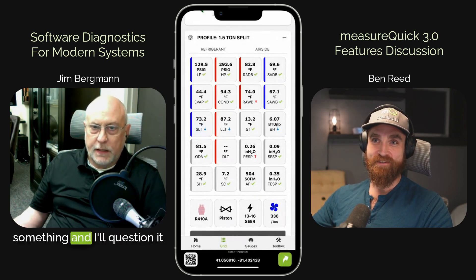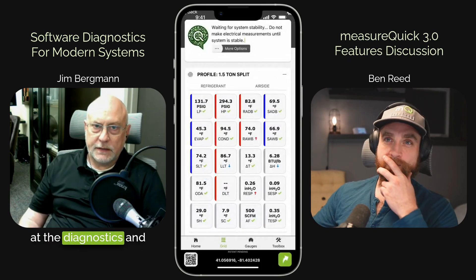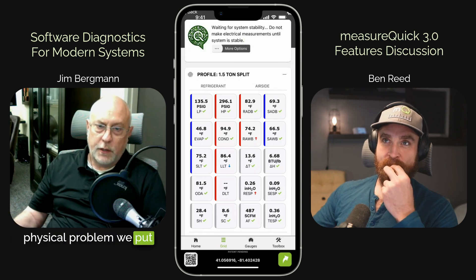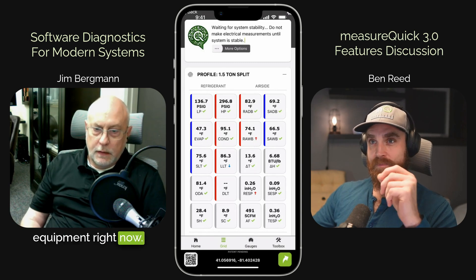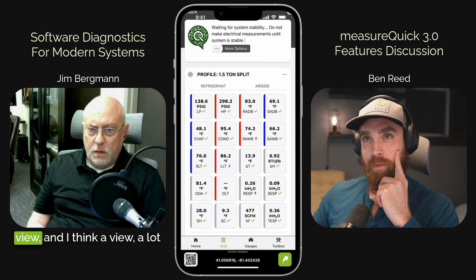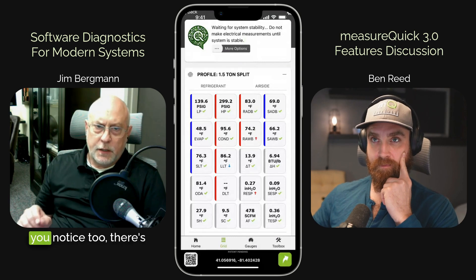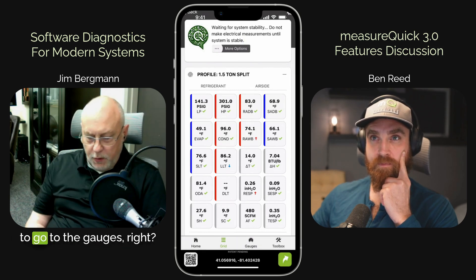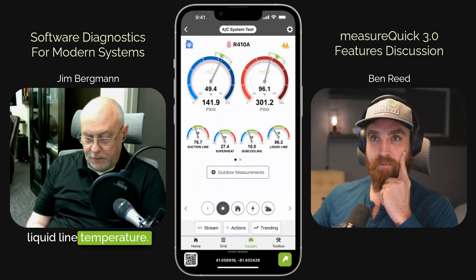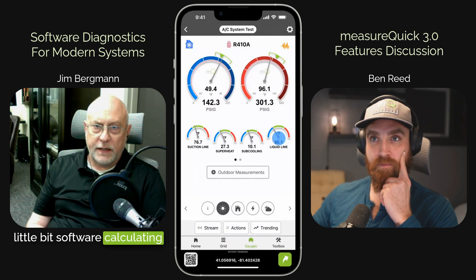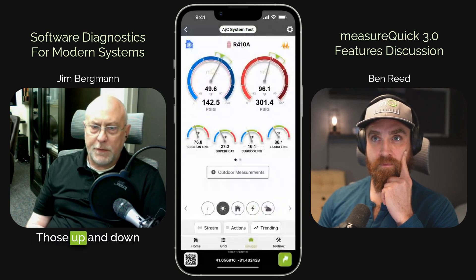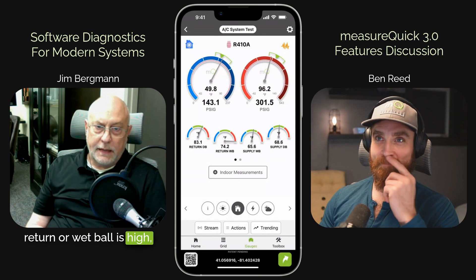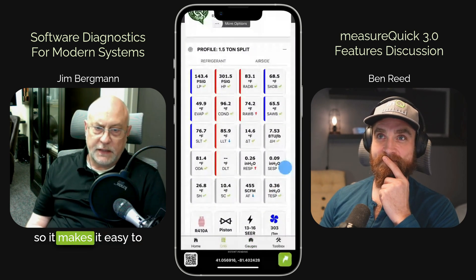I designed the software and a lot of times I'll be looking at something and I'll question it myself — what could be wrong with this thing? — and I'll go in and look at the diagnostics and either confirm what I thought I saw or go, oh yeah, that makes sense. Each one of these things is a real physical problem we put into real equipment; we're running on real equipment right now. And you notice there are check marks next to a bunch of readings, and you'll see an up arrow on the return air wet bulb and a down arrow on the liquid line temperature. Those are telling you — if you go to the liquid line temperature on the gauges — you can see that liquid line temperature is right on the threshold of being a little bit low. So those up and down arrows correspond: if it's green, it's a green check mark; if it's red, it's high; if it's blue, it's low. The return air wet bulb being high is the same exact data, just presented in a different way. So it makes it easy to understand and easy to use.